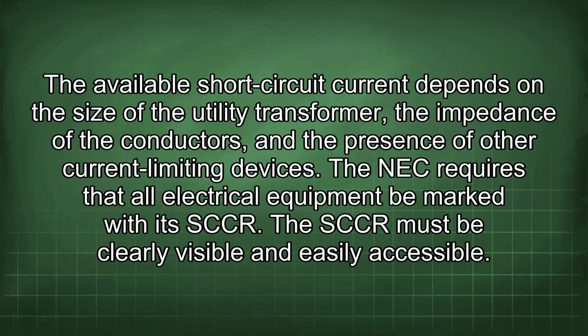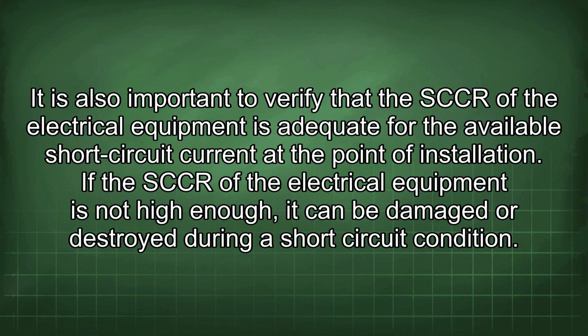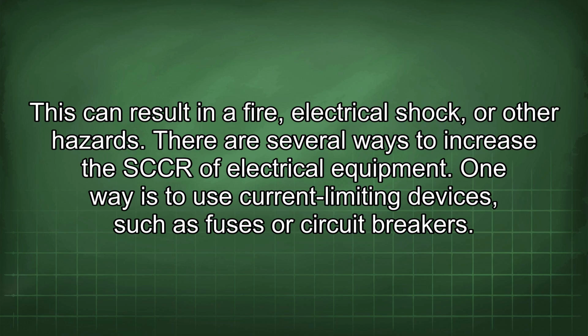The NEC requires that all electrical equipment be marked with its SCCR. The SCCR must be clearly visible and easily accessible. It is also important to verify that the SCCR of the electrical equipment is adequate for the available short circuit current at the point of installation. If the SCCR of the electrical equipment is not high enough, it can be damaged or destroyed during a short circuit condition. This can result in a fire, electrical shock, or other hazards.